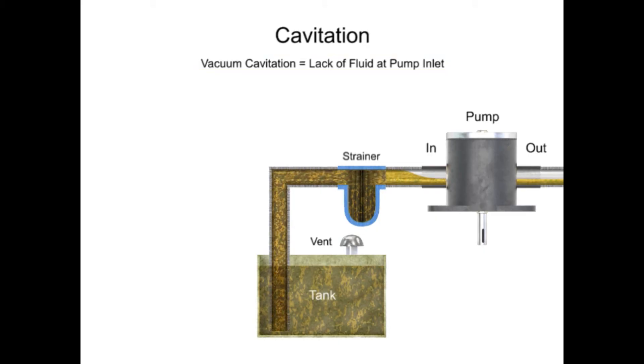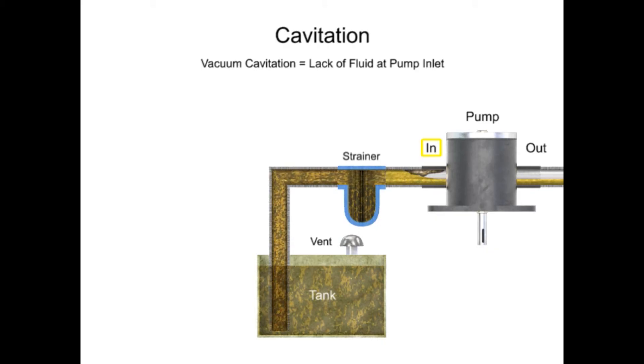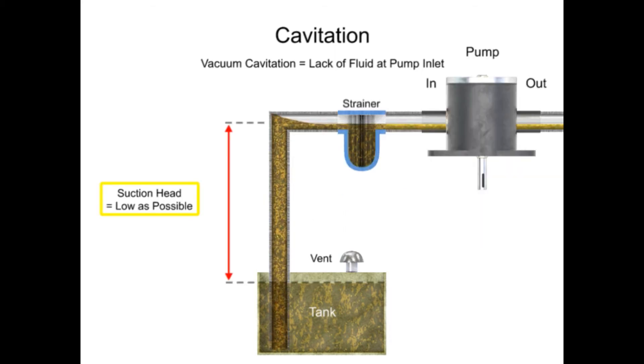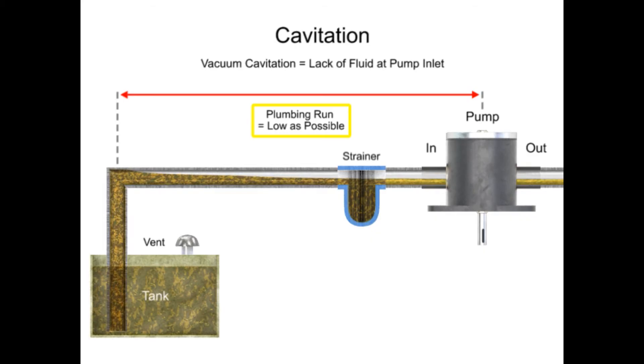The lack of sufficient fluid can be caused by a clogged inlet, a dirty strainer, or too large a suction head.